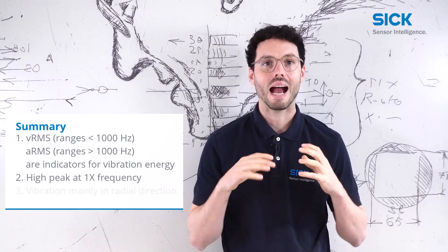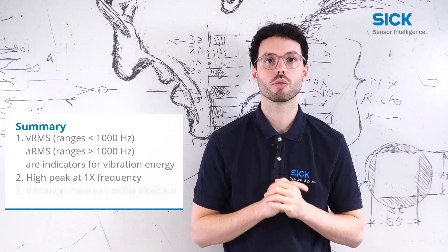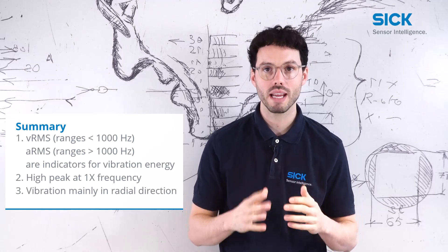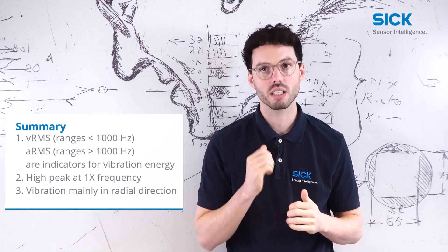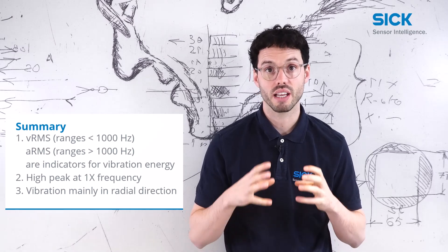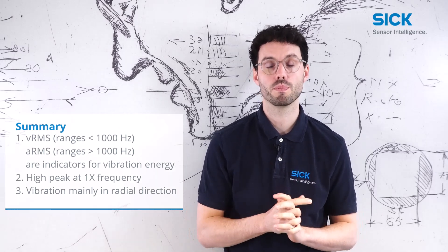A high peak at the rotational speed frequency and the vibration mainly in radial direction are good indicators that there is an imbalance problem.